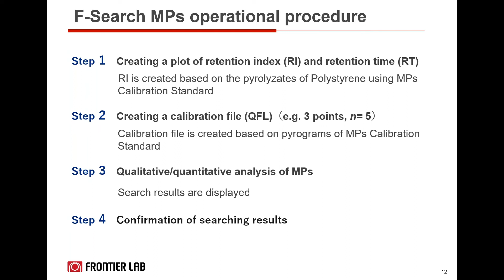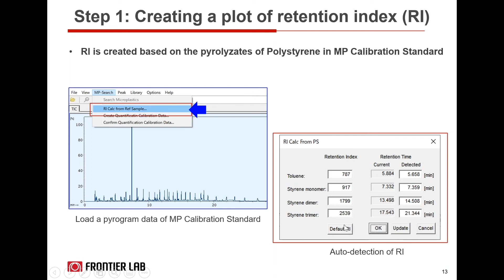In step 1, you load your sample and then do the RI calculation, which is based on the pyrolysate of polystyrene. You'll see that the system automatically does an auto detection of the RI, but you can also change the values, especially the retention time, in case you want a slightly different retention index. But the system will automatically do the RI.